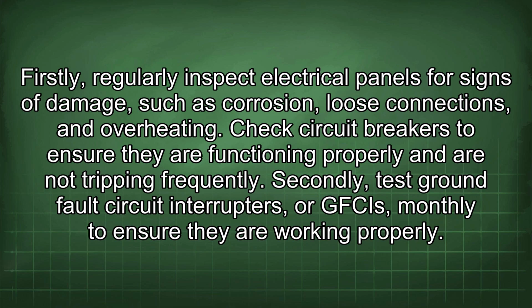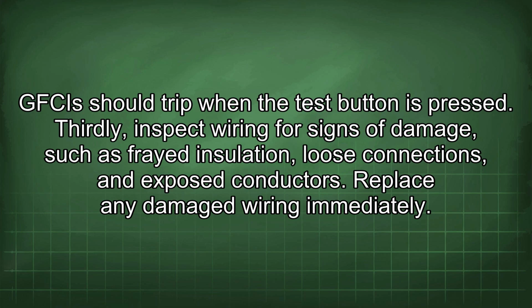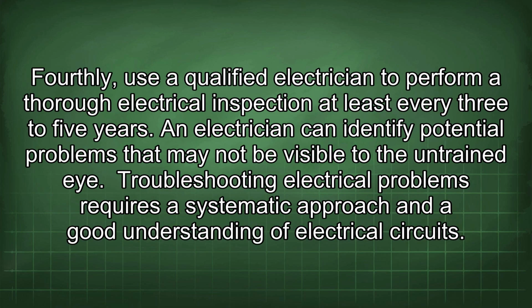Secondly, test ground fault circuit interrupters, or GFCIs, monthly to ensure they are working properly. A GFCI should trip when the test button is pressed. Thirdly, inspect wiring for signs of damage, such as frayed insulation, loose connections, and exposed conductors. Replace any damaged wiring immediately. Fourthly, use a qualified electrician to perform a thorough electrical inspection at least every 3 to 5 years. An electrician can identify potential problems that may not be visible to the untrained eye.